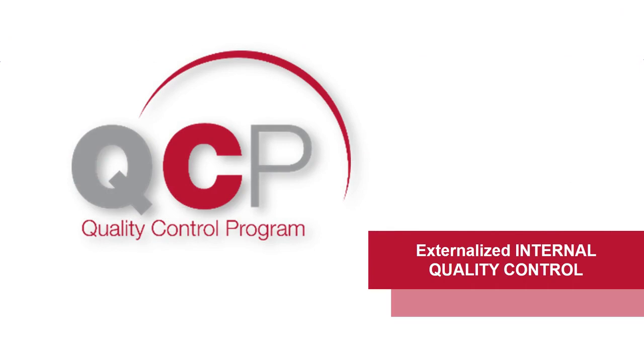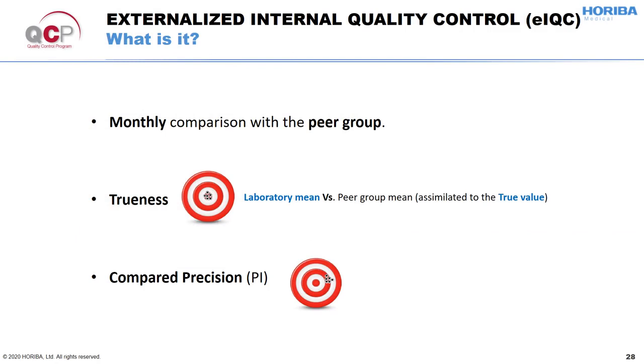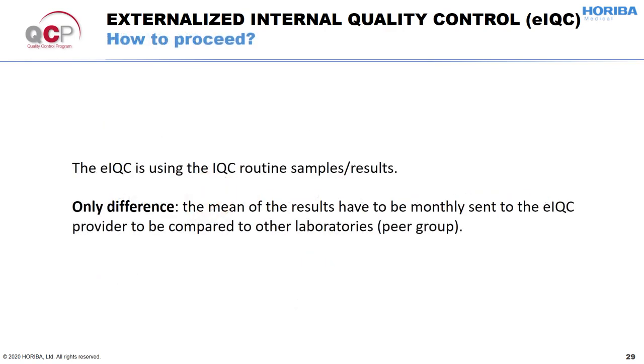Then we have the externalized IQC. This quality control will allow to monthly assess the trueness and precision by comparing the results to the peer group. The externalized IQC will not require additional control samples, as the laboratory can use its daily internal controls. It will just have to send the results to the externalized IQC provider to obtain its peer group comparison.